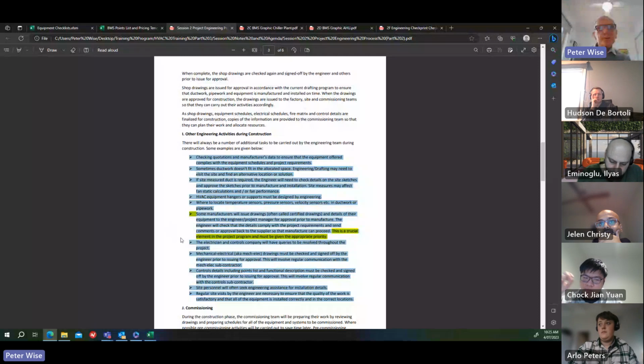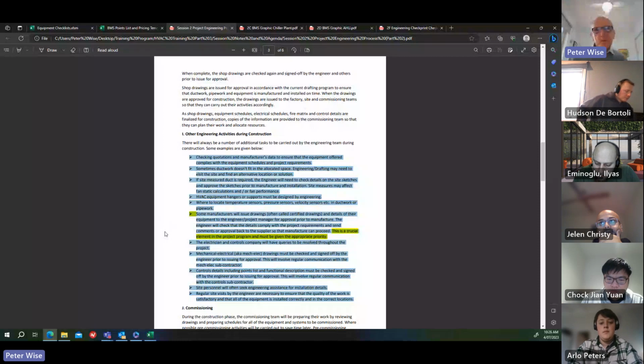This is a crucial element in the project program and needs to be given appropriate priority. So the manufacturer, let's say it's a chiller, and you've told them where you want the pipe connections, which is normally called the handings, which end you want the pipes on, and whatever else you need on the chiller. That will be on their drawings. You need to have a look at those drawings, make sure everything that you've asked for is shown, and then sign it off. If it's not shown, then you need to get back to them and get them to fix their drawings.